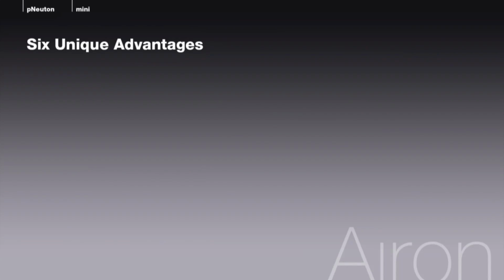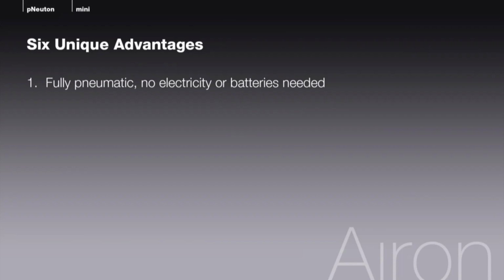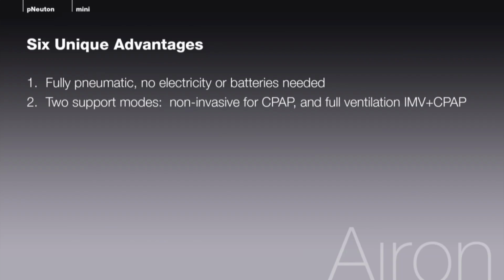Six unique advantages of the pNeuton mini include fully pneumatic operation, meaning the device runs strictly on a high-flow gas source, both oxygen and medical air, and requires no electricity or batteries for operation. Two support modes: non-invasive respiratory support using nasal prongs or masks for CPAP application, and full ventilation, IMV plus CPAP, with endotracheal tube. MRI compatibility with no Gauss line restrictions. The ventilator can be placed right next to the MRI magnet with a remote alarm for enhanced patient safety.